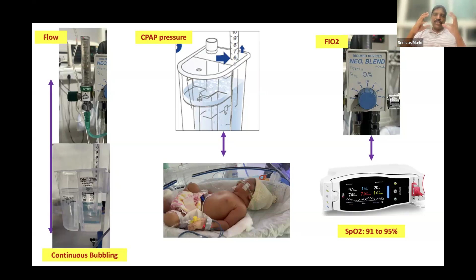So overall, when you are having hypoxia, that is saturation less than 90%, and the baby is showing that his lungs are still not open, that is, recessions are still there, what you need to do is keep increasing the pressure from 5 to 6, 6 to 7, 7 to 8, till you get a decrease in SA score. So once your SA score has decreased and your lung is optimized, then if hypoxia is still there, you increase FiO2. So if saturations are less than 90% and your SA score is 3 or less than 3, then you keep on increasing the FiO2 from 30 to 35 in steps of 5 till a maximum of 60%, so that you get a good saturation of 91 to 95%. So flow is for bubbling, pressure is for retractions, and FiO2 is for saturations after taking care of retractions.